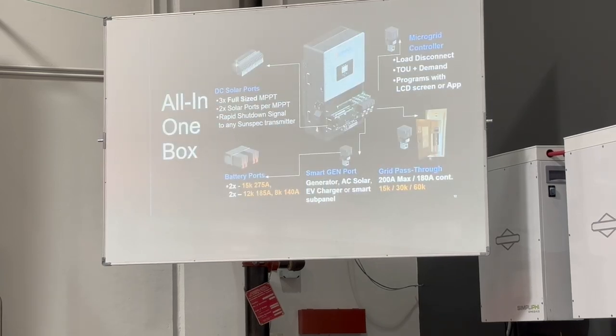As Nathan was touching on before, DC solar ports: there are 3 full-size MPPTs that have 2 solar ports on each, so 6 strings total. I don't know if you consider them strings, but I would. Typically you want those pretty evenly matched with those strings. If you have 20 panels, you probably want to do 10 and 10 per MPPT. When you're matching solar strings, it's important that the voltages match. So each MPPT, you can bring in 2 strings, and it's important to match the voltage.